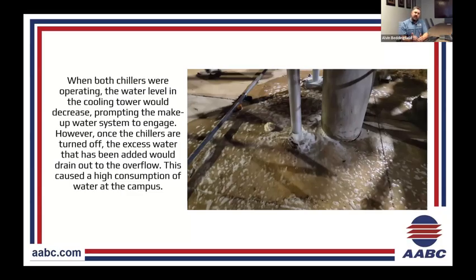Okay, well, now that the piping's been reconfigured, now we've got to go back and set the water flow. Well, this one's getting too low. We're starting to cavitate. So we'll go back to the other school. Yep, we're cavitating over here, so let's raise the water flow. And it was just nonstop action. Like, we resolve one issue at one school and we'll go to the identical school and say, okay, let's tackle the same issue. Okay, now we're tackling the same issue. We'll go back to the other school. Here's the next issue. Let's keep troubleshooting.